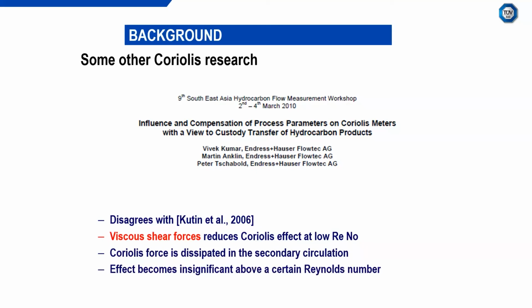So they do a calculation of the uncorrected Reynolds number. They use the uncorrected mass flow. They also know the tube dimensions. They know the fluid density from the frequency, and they can infer viscosity as well from the Coriolis flow meter outputs. They use all these uncorrected values to get an uncorrected Reynolds number. So it could be out by say 5, 10, 15%, but that gives them an approximation.